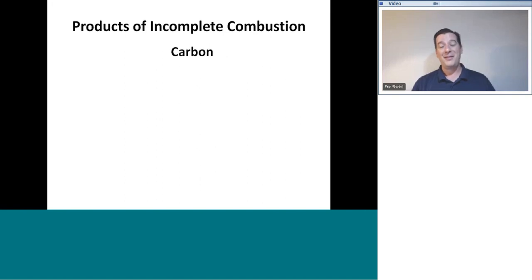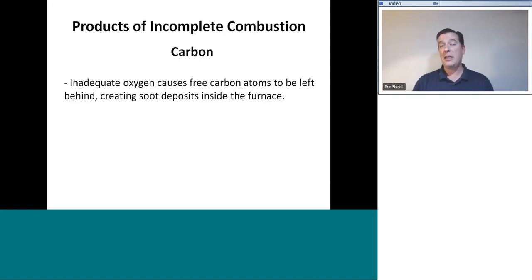Straight up carbon can be a product of incomplete combustion. Natural gas should burn very cleanly. There should be no soot or residue left behind. But if we have a situation where we are severely inadequate in the oxygen supply, severely inadequate combustion air supply for the amount of fuel being consumed, this is going to cause free carbon atoms to be left remaining at the end of the combustion process. And they're just going to be floating around, sticking on stuff, leaving behind a black soot deposit. If you look at a natural gas burning appliance and you see black soot near the burners or in the combustion chamber of that appliance, you have a serious combustion problem.